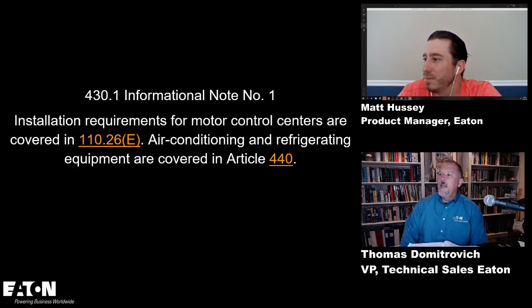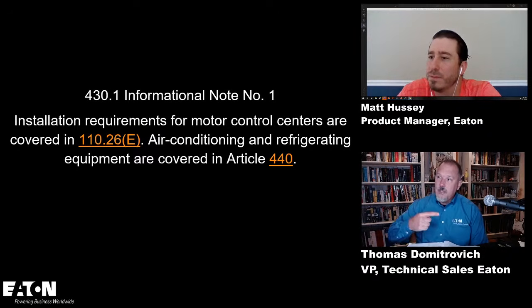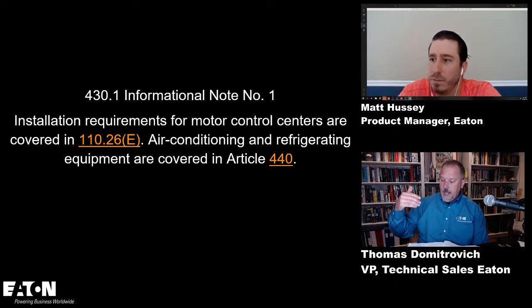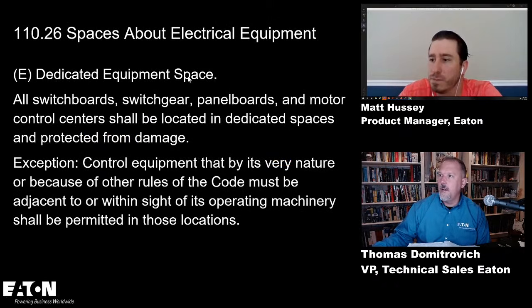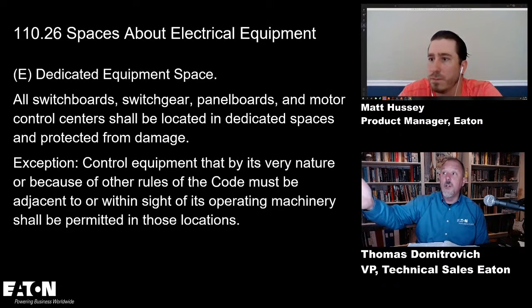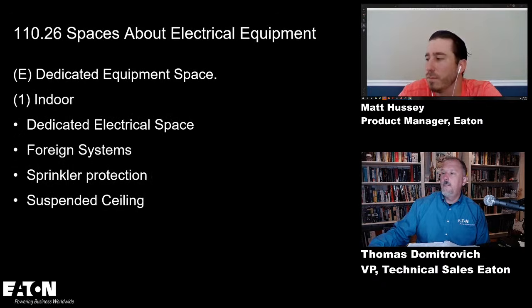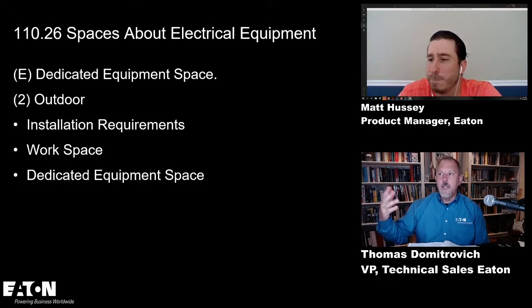But all right. Now, 430.1 informational note points us back to 110.26(E), telling us that installation requirements for motor control centers are covered in 110.26(E), which, if you look at it, says dedicated equipment space, and this is what's talking about your indoor and outdoor locations. I think I put the titles in there. Dedicated equipment spaces, but it covers also switchboards, switchgear, and panelboards. MCCs are in there. And then you have your indoor: you talk about dedicated electrical space, foreign systems, sprinkler protection, suspended ceiling, and then you have your installation requirements, working space, dedicated equipment space.